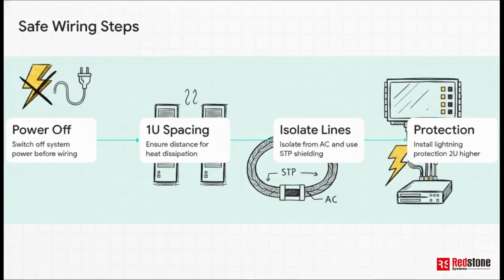So here is your essential survival checklist for safe wiring. Step 1, always cut the power first before you begin wiring, and only turn it back on once you're fully done. Hot wiring causes immediate system malfunctions. Step 2. Ensure that 1U spacing for heat dissipation before you lock the device into the cabinet. Step 3. Isolate your voice lines from AC power and use that STP shielding we mentioned.